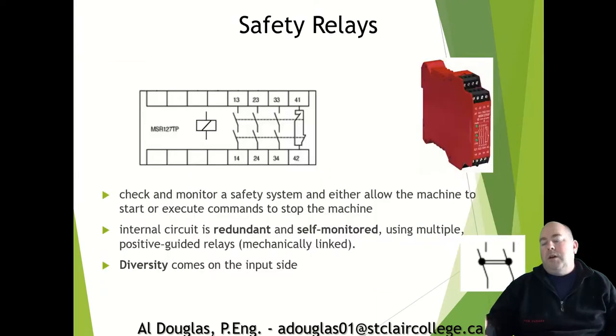Now what we have done as technology has advanced, we've created these devices called safety relays. So this basically contains all that same circuitry, but in one very small device that we can wire. These things are physically typically about 22 millimeters wide, so they're not very big.